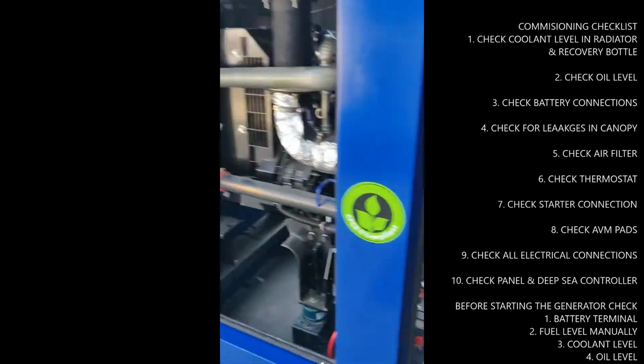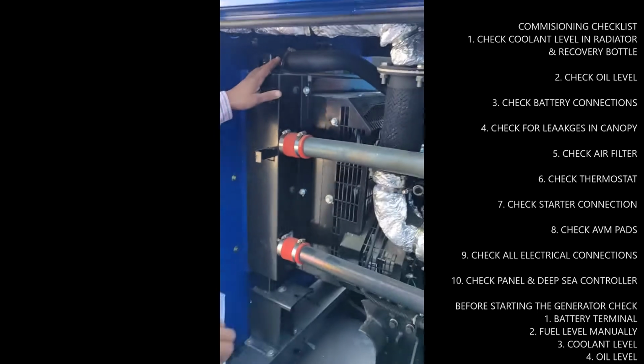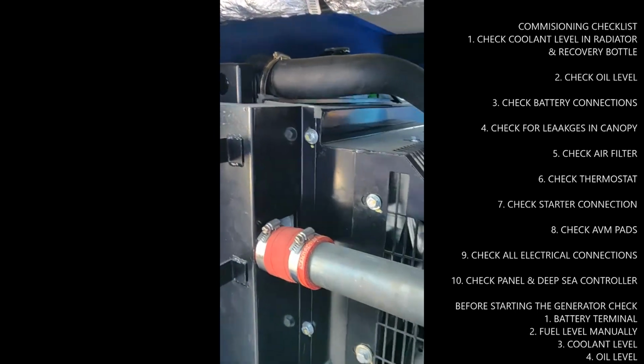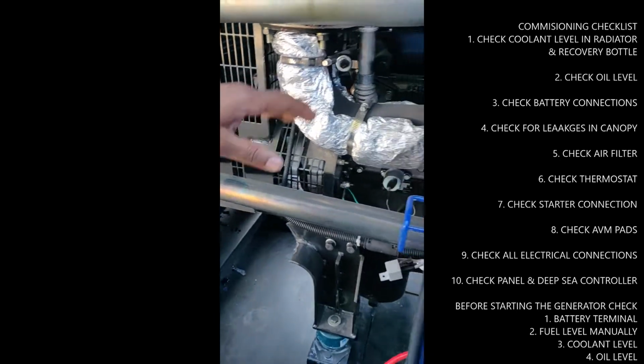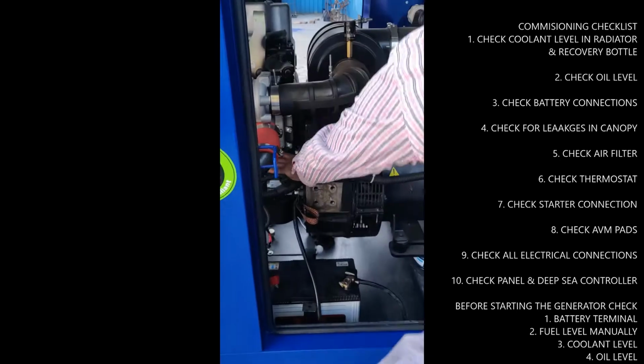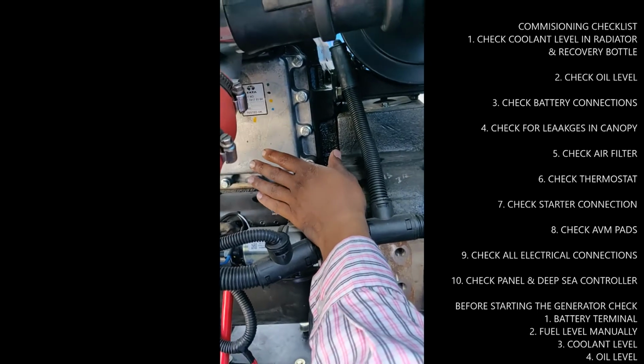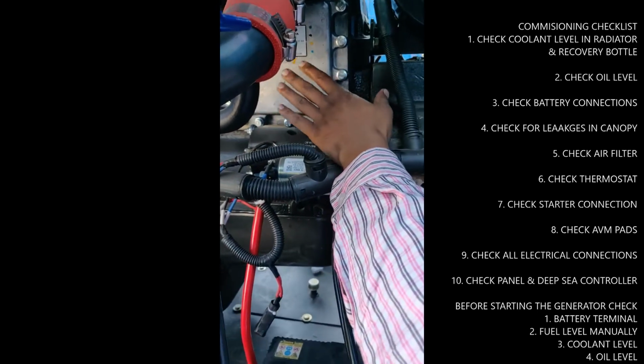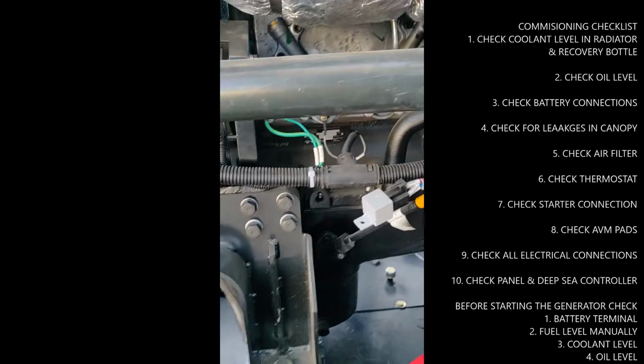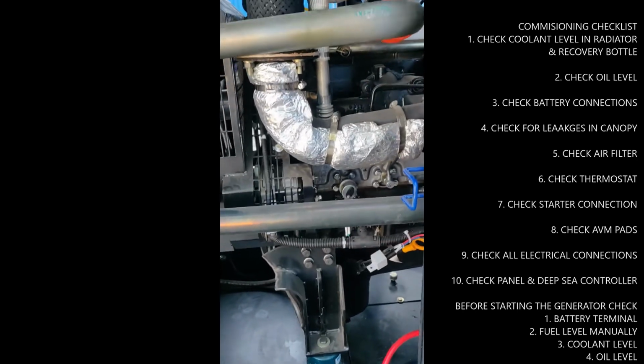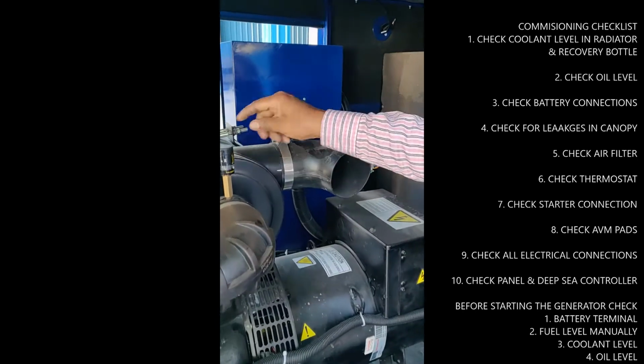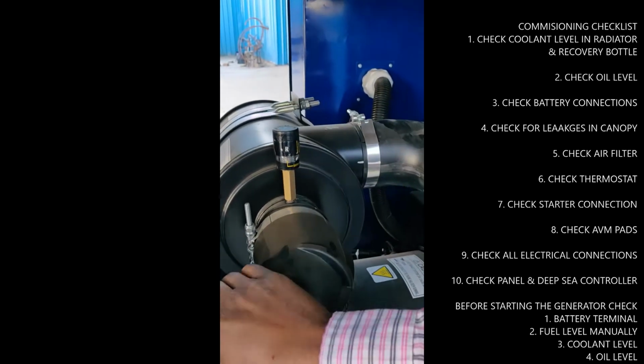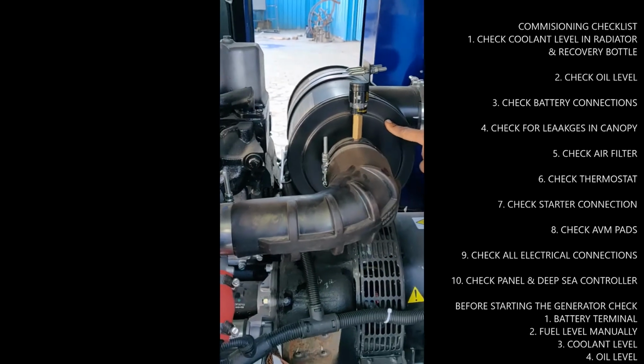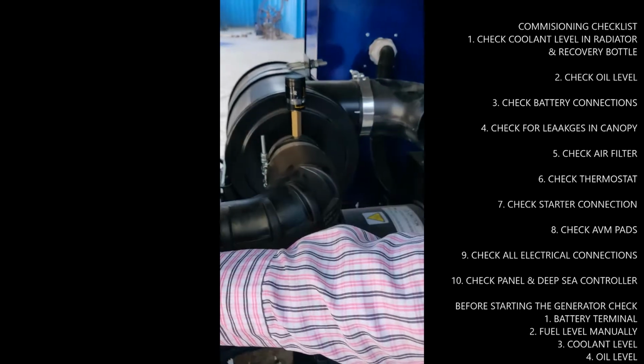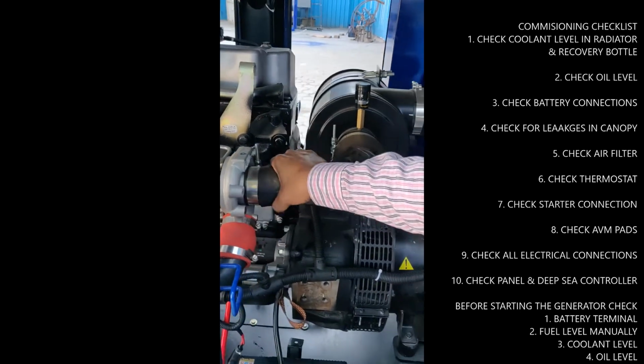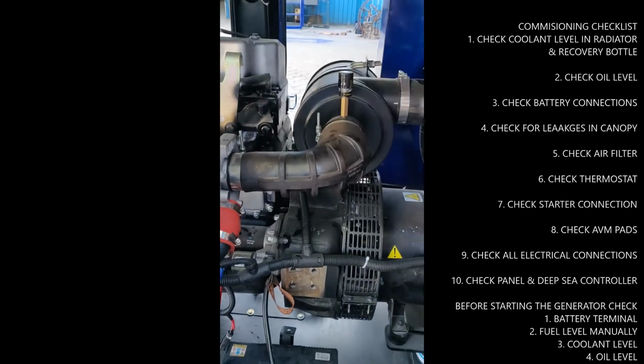Now check for any leakage in the canopy. You can check the hoses. Check that all of them are tightly bolted and properly fitted. The connections are proper. Please make sure to check all the hoses, the sensors and the electrical connections are properly connected and not loose at all. This is the air filter. Air filter hose is then connected to the turbocharger. Please check that they are properly bolted and tight at all times.